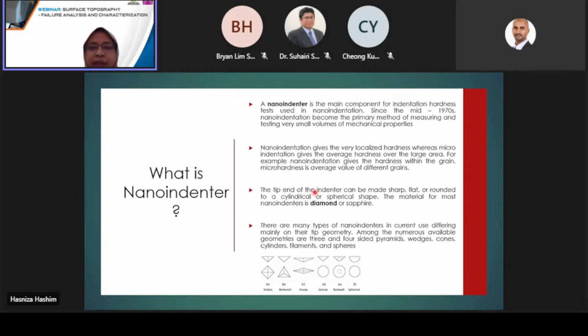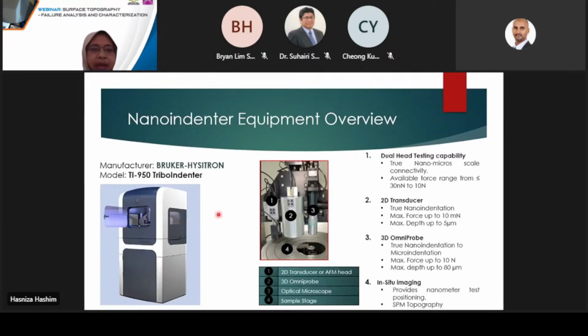And the tip of the indenter can be sharp, flat, or rounded to a cylindrical or spherical shape, and is normally made of diamond or sapphire. There are many types of nano indenters in current use, differing mainly in their tip geometry. In our lab, we are using the Berkovich tips. Here are a lot of specifications about our instrument, which is the Bruker Hysitron TI-950 Triboindenter.